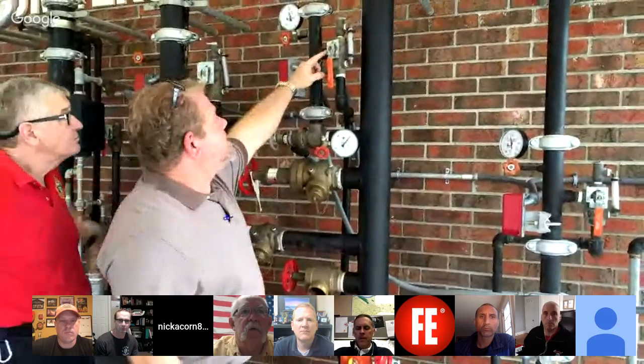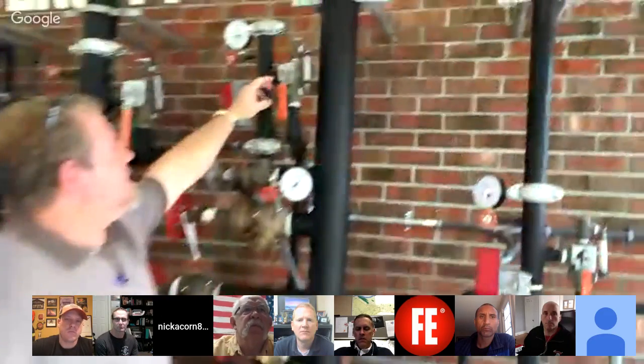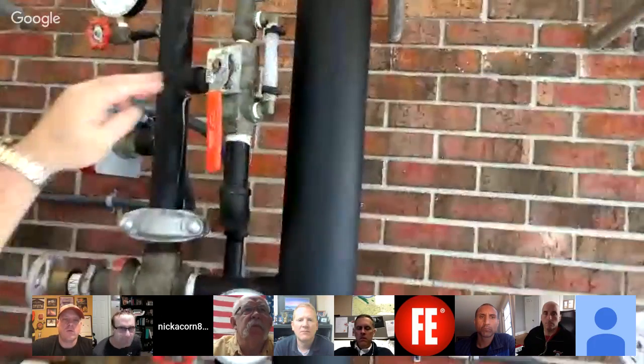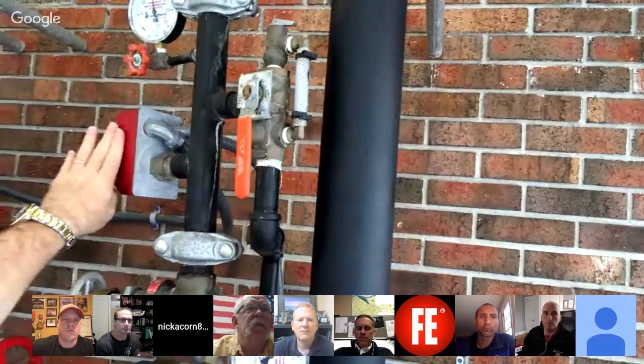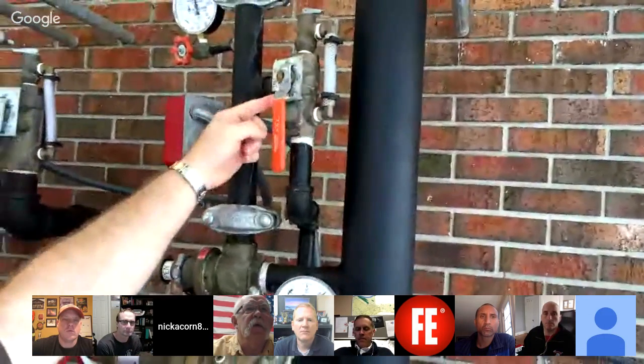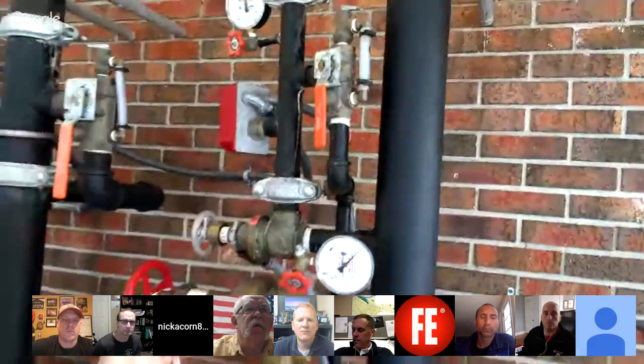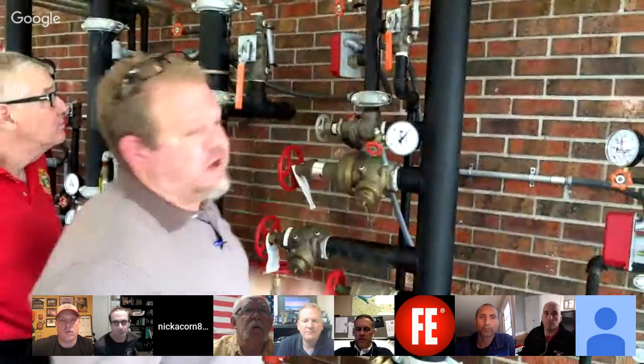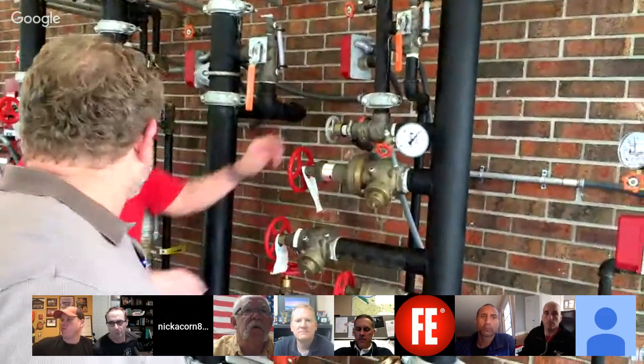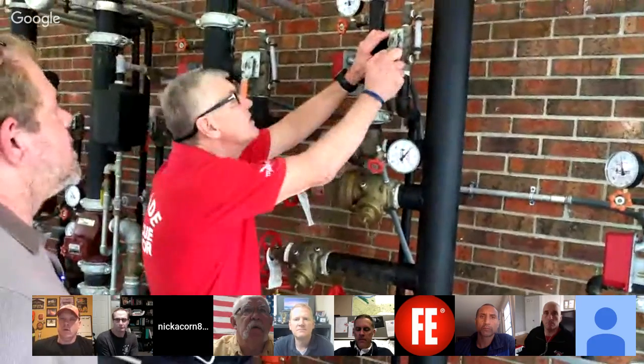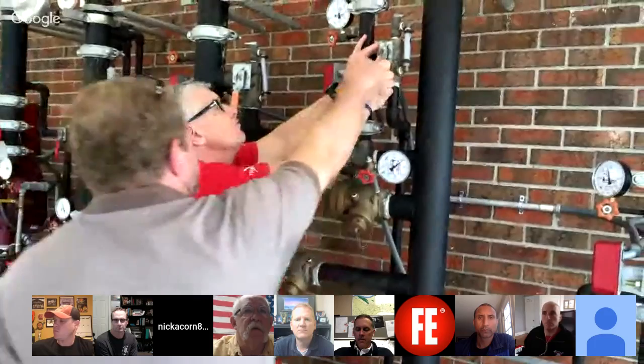And then what we have is 2 different applications. We have a test, which in this function tests the flow switch. And what we're actually able to do is push the button and take it into a drain scenario. So we'll actually drain the sprinkler system. So close the water supply, isolate the floor, and drain the water off that floor. So the test would replicate the flow of one sprinkler. One sprinkler head. It's got a sight glass there.